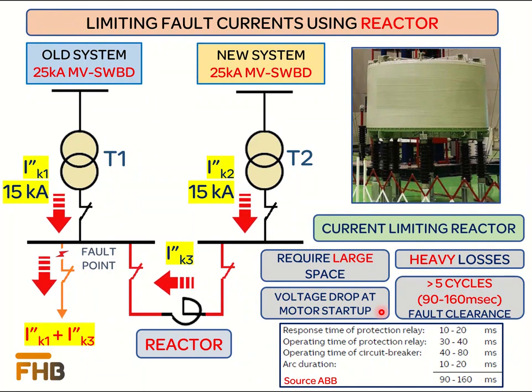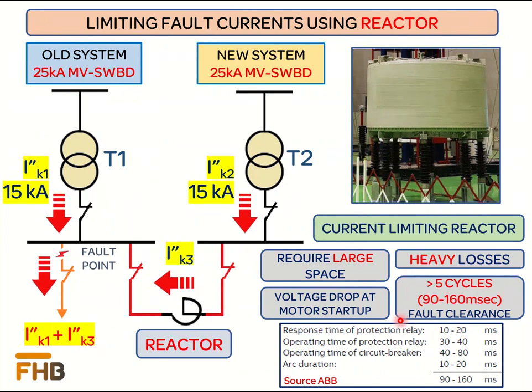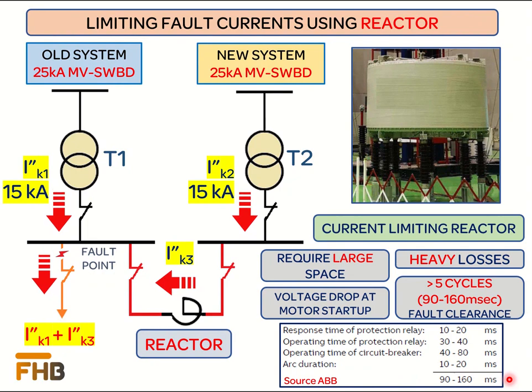Since current limiting reactors reduce the value of short circuit current but have no effect in reducing the fault clearance time, as per standard, fault clearance will take 90 to 160 milliseconds depending on the response and operation time of the protection relay, operation time of the circuit breaker, and the arc duration. By using current limiting reactors, there will not be any improvement in fault clearance time.